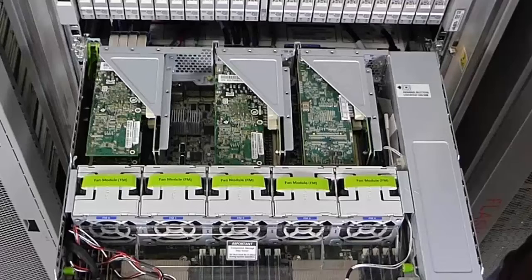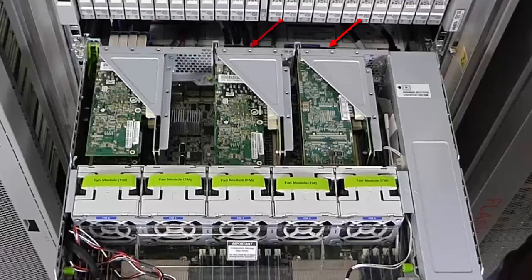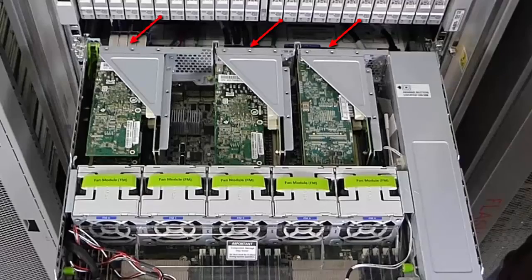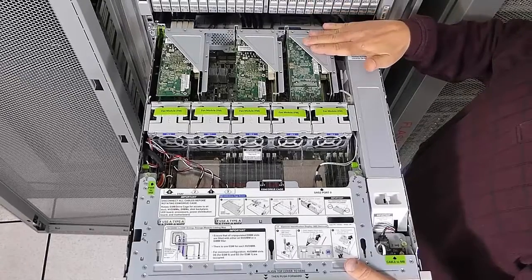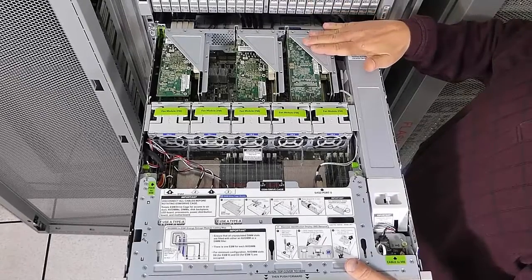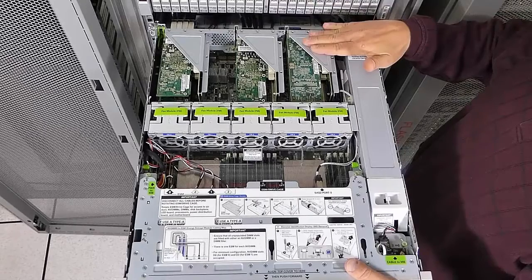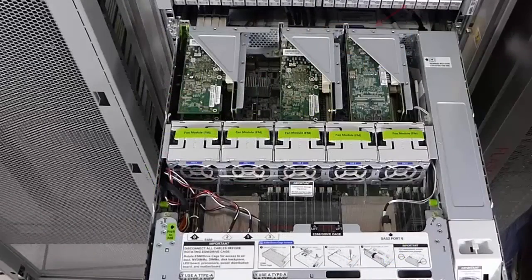Verify whether cables are connected to the HBA card that you plan to remove. Make note of the connected ports and then disconnect the cables. In this example, we'll replace an HBA card in riser 1. The HBAs in riser 1 in this system do not have connected cables.